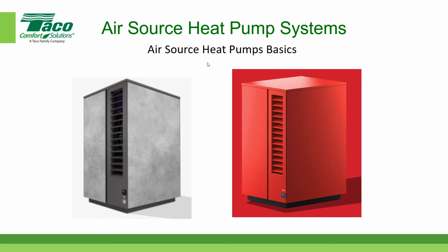Essentially, by the way, just to make sure everyone understands, since you're talking about the COP, the output for a convention for an air to water heat pump, the COP is greater than 1. The COP, although we don't use this term in resistance electric heat, is 1. So in other words, if the air to water heat pump has a COP less than 1, it's more energy efficient to use electric resistance heat, because electric resistance heat has the same capacity output as the power input. In other words, 100% of the power can be converted into heat. I forgot to mention that.